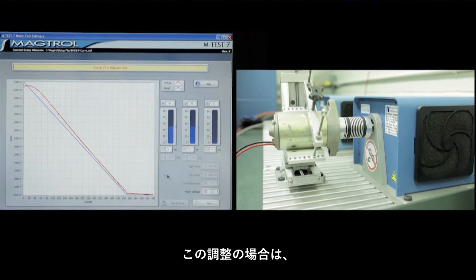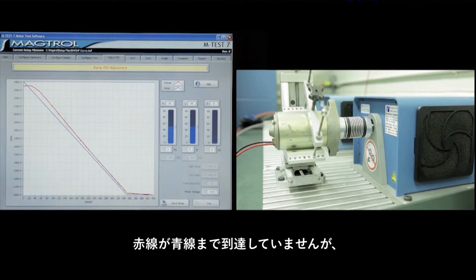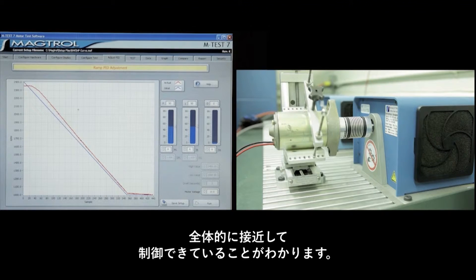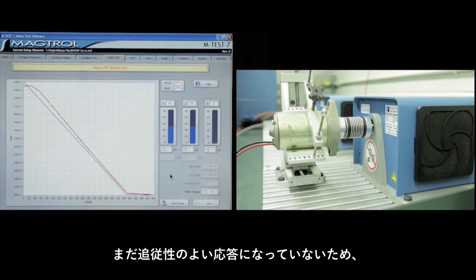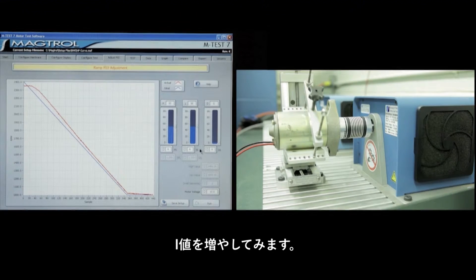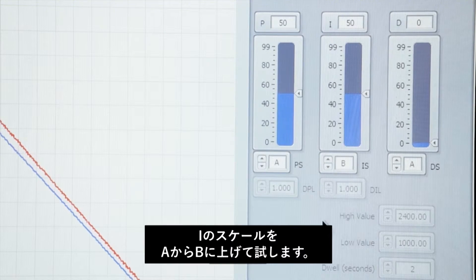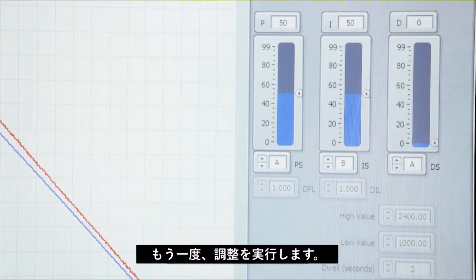In this case the red line did not touch the blue line, but it was fairly close to it throughout the whole adjustment range. That is not ideal response, so what we want to do is increase the I term.